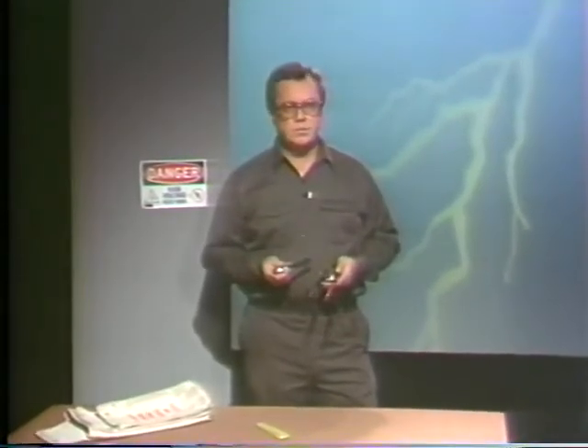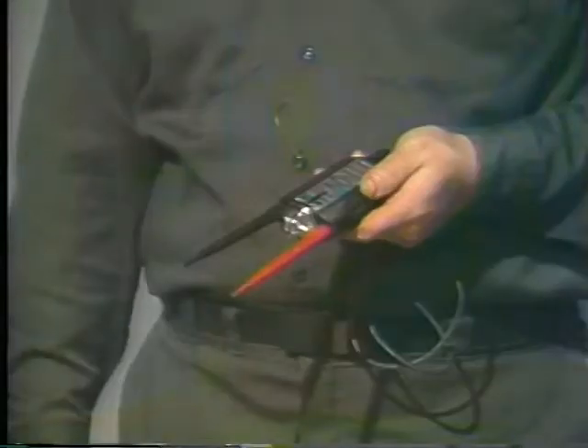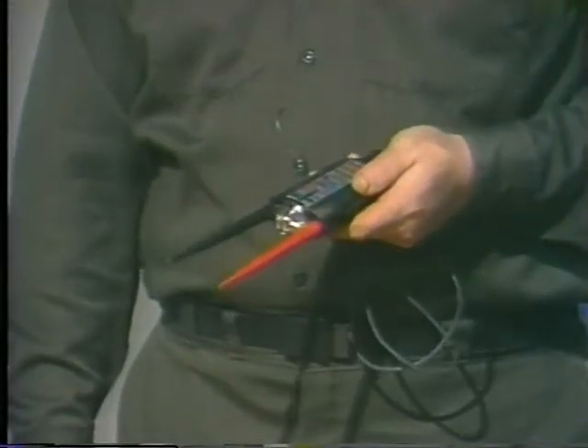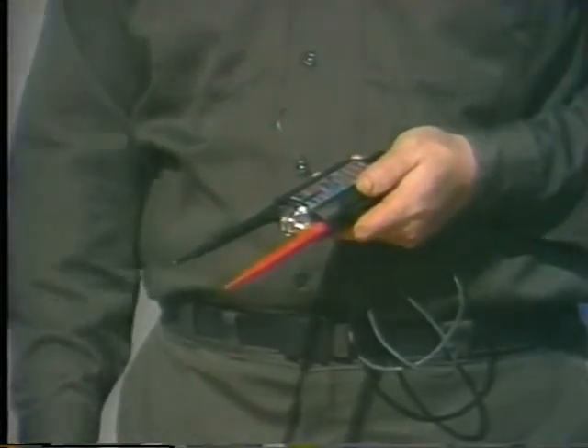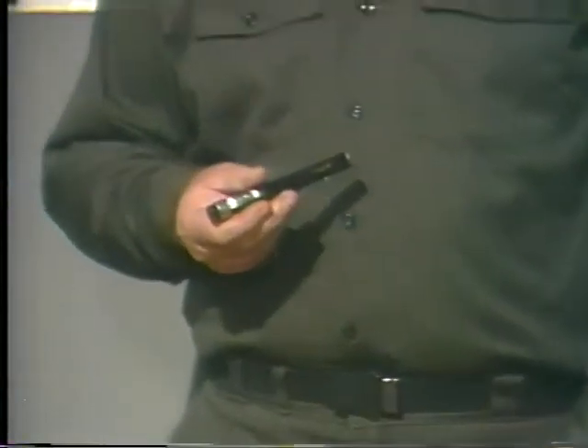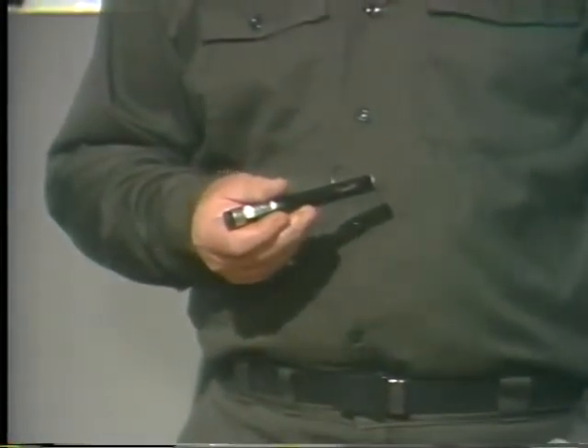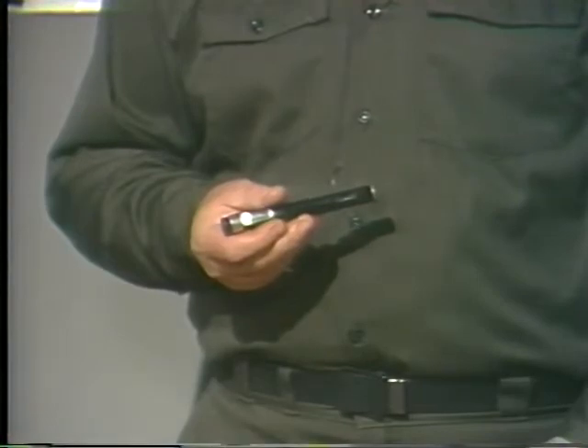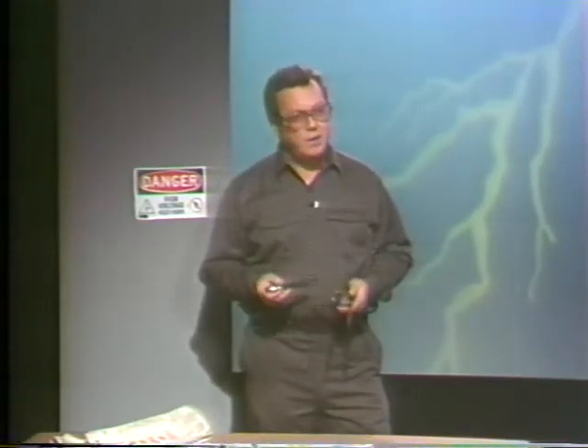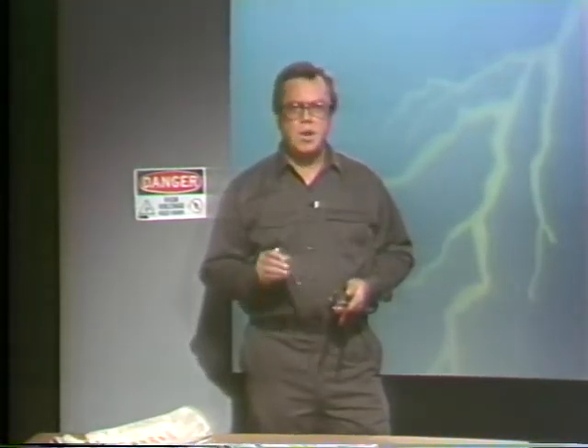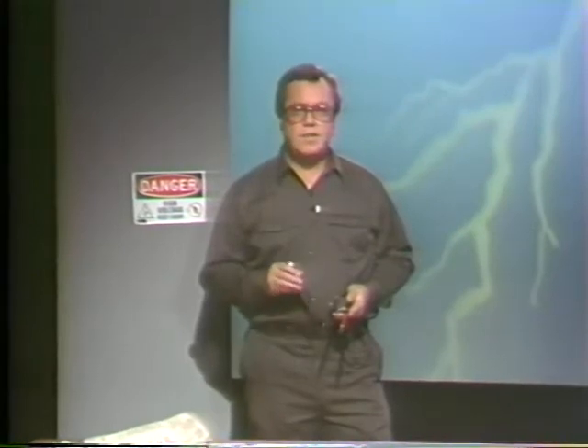The first thing to know is what detector to use. A low voltage device like this one might explode if you tried it on a 14 kV line. And a high voltage model won't necessarily give you any indication at all if you're trying to detect as little as 220 volts. I'm not going to give you any hard and fast rules here because there are a lot of different voltage detectors on the market. All I can say is find the approximate voltage range and use a detector that'll register in that range.